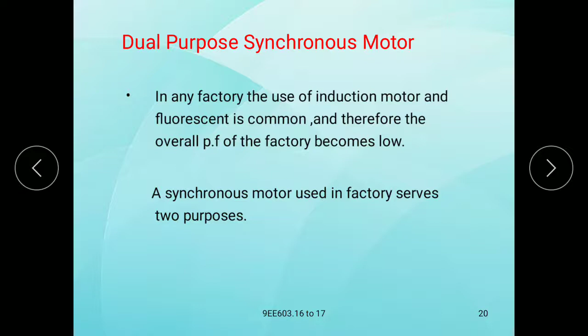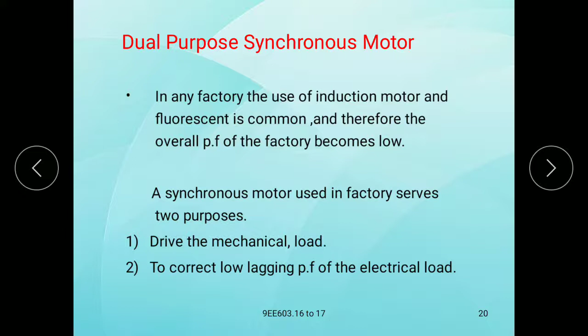Here, the dual purpose of a synchronous motor: in any factory, the use of induction motors and fluorescent lamps is common, and therefore the overall power factor of the factory becomes low. A synchronous motor used in a factory serves two purposes: one is to drive the mechanical load, and the other is to correct the low lagging power factor of the electrical load.